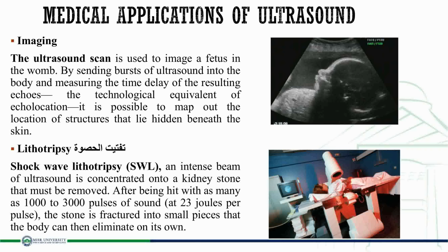Precisely. Sound waves carry energy. If you concentrate that energy, just like focusing sunlight with a magnifying glass, you can create intense pressure. In this machine, we focus an intense beam of ultrasound directly onto a kidney stone inside a patient. It says here 1,000 to 3,000 pulses at 23 joules per pulse. That sounds like a lot of energy.